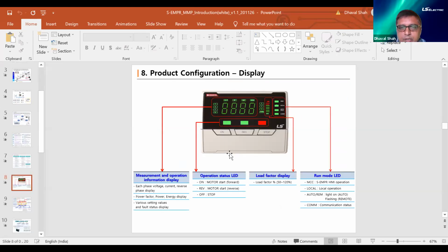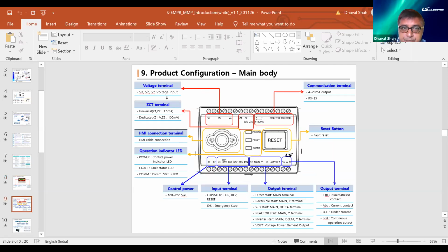So this is what the product looks like. This is the display of the MMP. On the left side, if you see, this is the measurement and operation information, which shows the voltage, current, reverse power, reverse phase, power factor, power energy display, and various setting values and fault level. Whereas here, part B shows the load factor display, which is 50 to 120%. Then these three indicators show on, motor start, motor reverse, and off position. And the extreme right shows the running mode condition, whether it is operated from local station, automatic, reverse, or communication. The main unit has so many terminals, and you can go through the details whenever you have free time. Voltage terminals, meaning all the input and output terminals, are there.